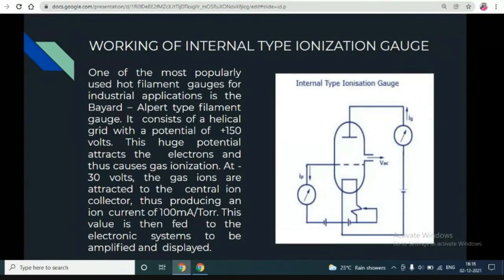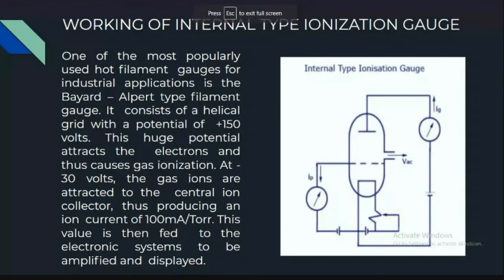Working of internal type ionization gauge. One of the most popularly used hot filament gauges for industrial application is the Bayard-Alpert type gauge. It consists of a helical grid with a potential of plus 150 volts. This high potential attracts the electrons and thus causes gas ionization. At minus 30 volts, the gas ions are attracted to the central ion collector, thus producing an ion current of 100 mA per torr. This value is then fed to the electronic system to be amplified and displayed.